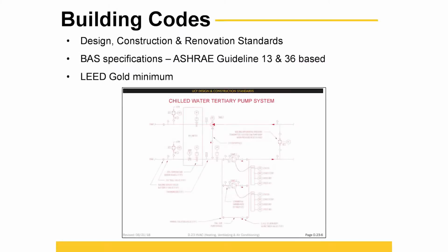We are very specific on our BAS specifications. We use ASHRAE Guideline 13 as a foundational document, and we're currently incorporating a lot of the sequence of operations, particularly alarms management, mentioned in ASHRAE Guideline 36.